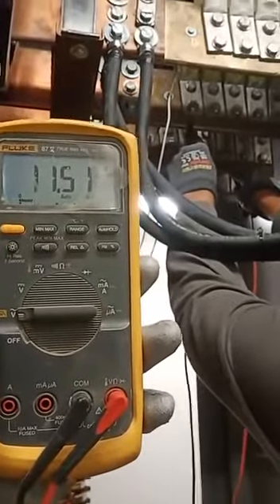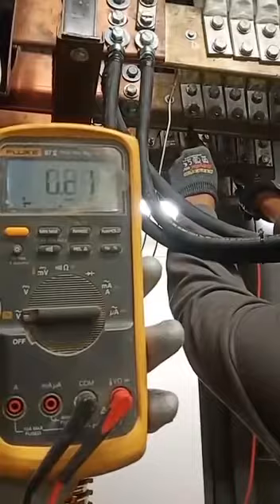Can you check again the result phase to phase? See, this is the result: 11.51 phase to phase. Next, phase to neutral is 6.6.